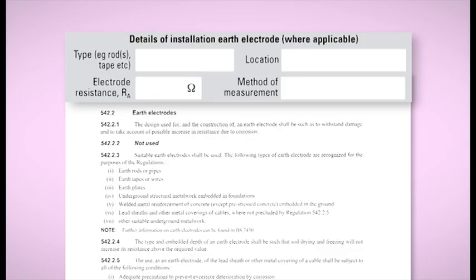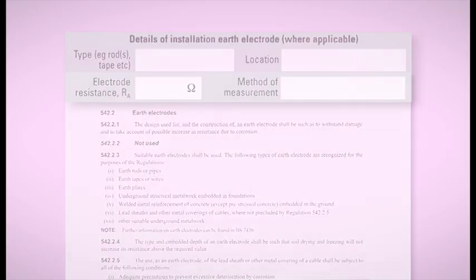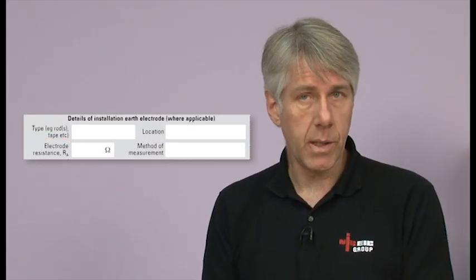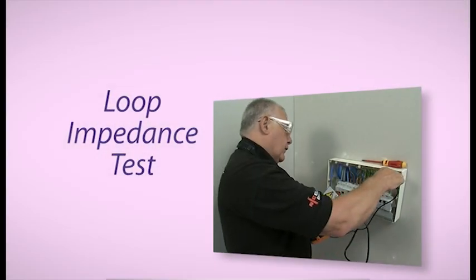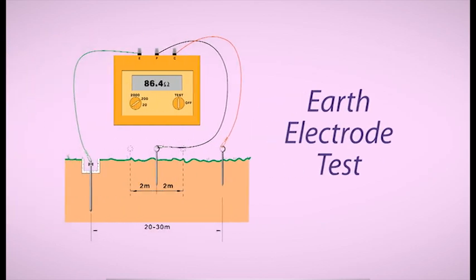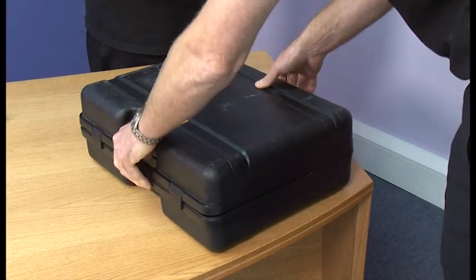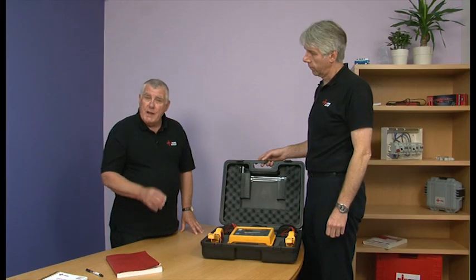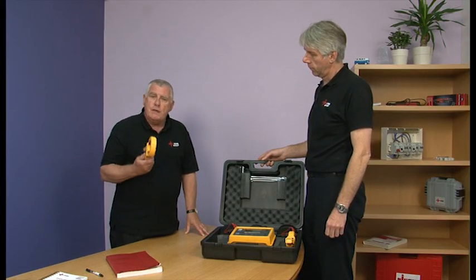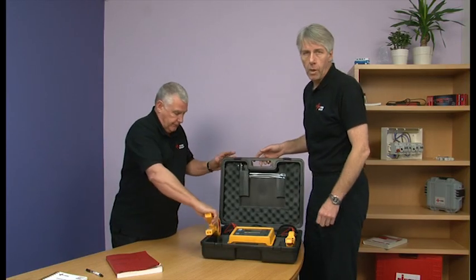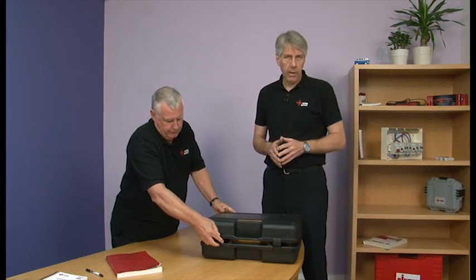If you're on a TT system, you'll have to fill in the remaining details about the installation earth electrode. The acceptable types of earth electrode are listed in Regulation 542.2.3. It will also be necessary to measure and record the electrode resistance RA, and you must also write down how this was measured, because there are several test methods that can be used. For example, where there's a supply, a loop impedance tester may be used, or where there's no supply, by using an instrument and proprietary earth electrodes to undertake the fall of potential method. However, recent developments in test equipment have also introduced a new non-invasive test where there is no need to disconnect the earthing conductor or connect to live terminals. You can instead use clamps. So an overall safer approach to obtaining the earth electrode resistance. Remember that the resistance value you get should be as low as practicable, and that values above 200 ohms may become unstable, particularly in dry or frozen conditions.